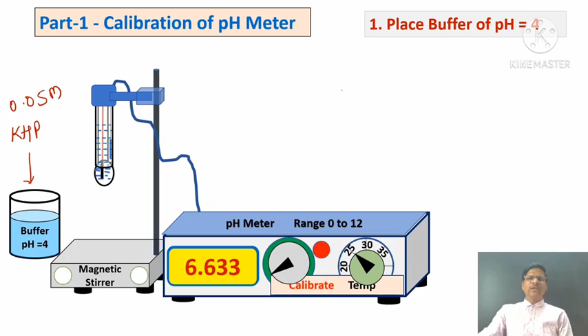Okay, so ultimately we have to place the electrode in the buffer solution. I will dip the electrode into the buffer solution, and now I will rotate this calibration knob. This is the calibration knob. Till pH becomes 4.005, I will rotate this knob slowly. Just look at the animation. You can see the rotation has started, and corresponding to this there is a change in values.